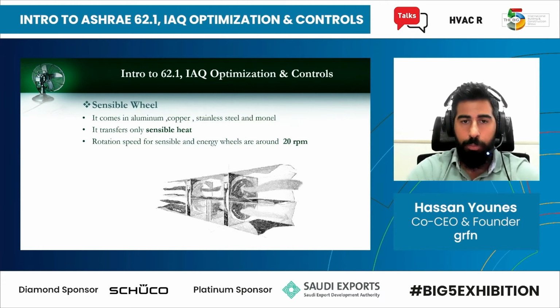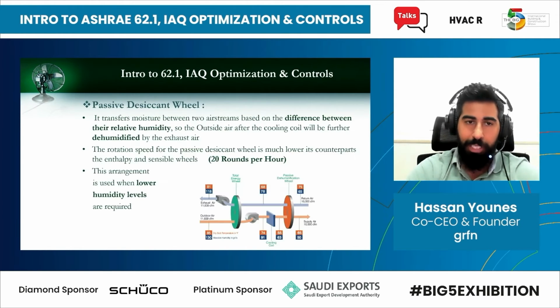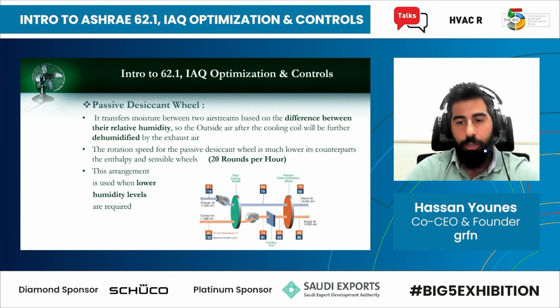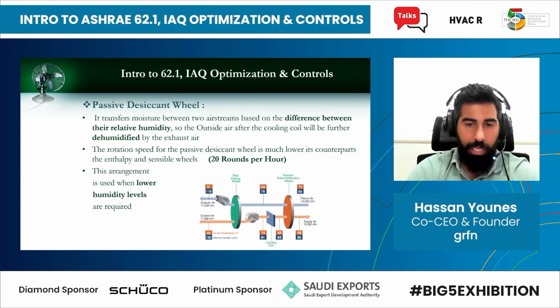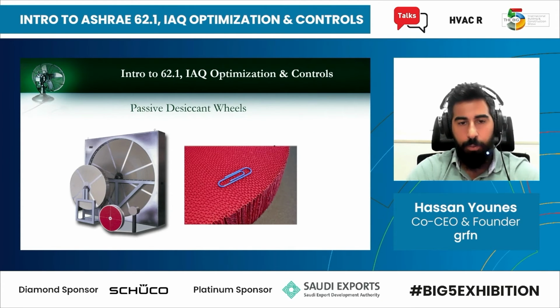The sensible wheel normally comes in aluminum, copper, stainless steel, and monel, and it transfers only sensible heat. The rotation speed is around 20 rounds per minute. Passive desiccant wheel is another way: instead of the sensible heat recovery wheel, you can put the passive dehumidification wheel, and that will further dehumidify the outside air. So if you really want dehumidified air, that could be the solution. It's a bit more expensive, and that wheel runs at 20 rounds per hour compared to 20 rounds per minute for the other types of wheels. But it is a good option if you want really high dehumidification, or to get the outside air to a really low humidity level. This is kind of how it looks.